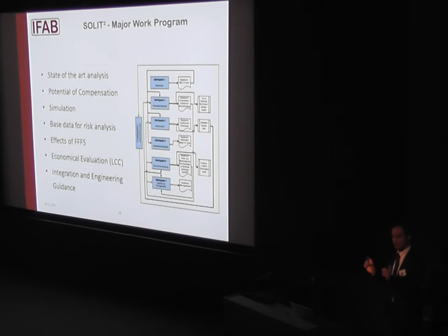There was also a big simulation component, because at the moment it's still mostly full-scale fire testing — as you heard this morning from FM Global, a very costly exercise. So in the future we want to reduce these costs and try to simulate, at least partly, the effects of firefighting systems. Some effects of fixed firefighting systems are also studied, and importantly, we do an economic evaluation between different types of systems — not only between firefighting systems, but between different parts of the tunnel safety system. If you want to compensate part of the ventilation with another system, you need to know the costs, including not just installation but life-cycle costs for both systems, so you can properly compare them.